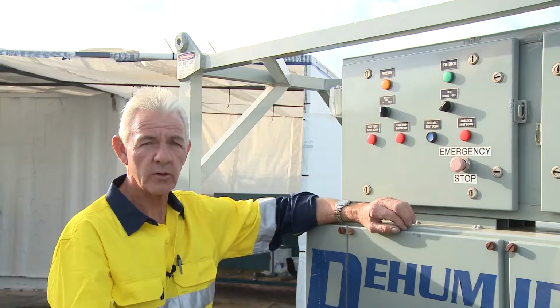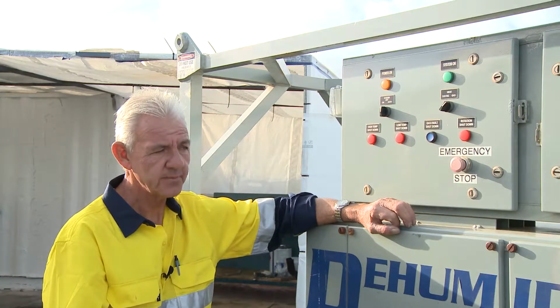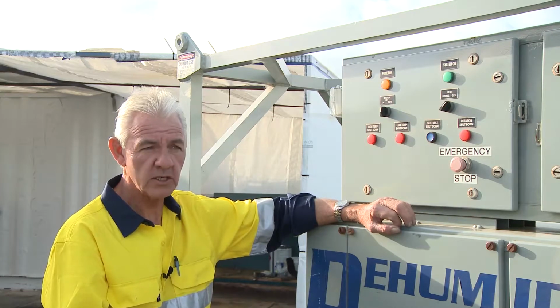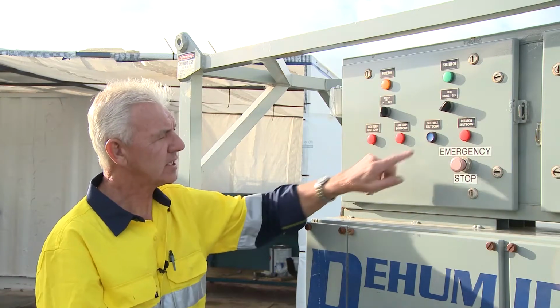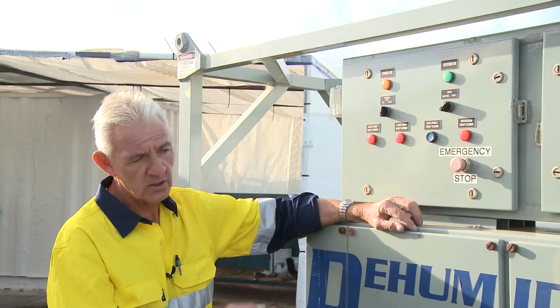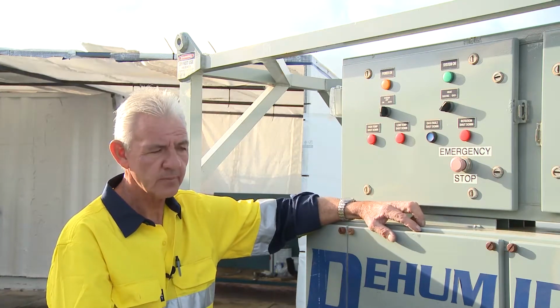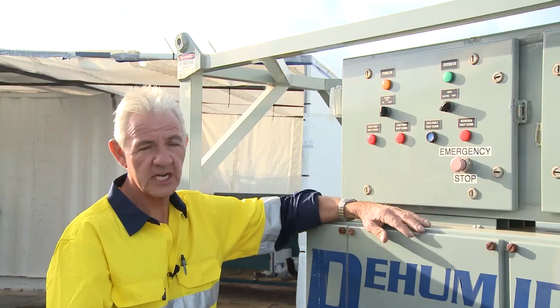So say, for example, your genset runs out of power, you run out of gas, your filters are blocked, you'll start to see the illumination of some of these lights. A gas fault, basically same thing. You've run out of gas, the regulators are dirty. So how do I eliminate the illumination of any of these or the machine shutdown?